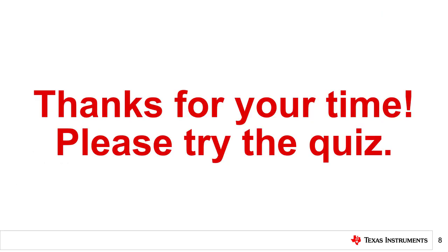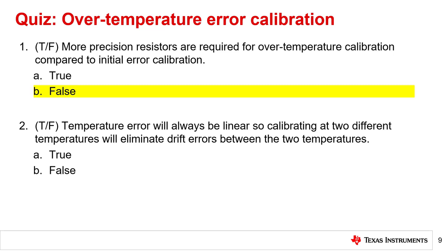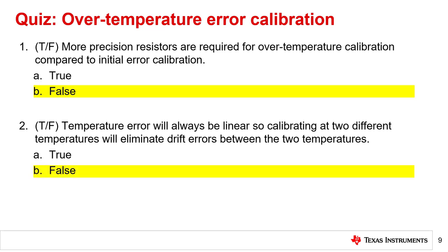That concludes this video. Thank you for watching. Please try the quiz to check your understanding of this video's content. Question 1: True or False? More precision resistors are required for over-temperature calibration compared to initial error calibration. The correct answer is B, false. For a given RTD type and measurement range, only two precision resistors are required for either initial error or over-temperature error calibration. Question 2: True or False? Temperature error will always be linear, so calibrating at two different temperatures will eliminate drift errors between the two temperatures. The correct answer is B, false. Temperature error can be non-linear such that calibration can reduce error between two calibration points, but not necessarily eliminate it.